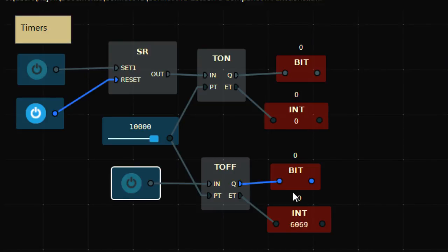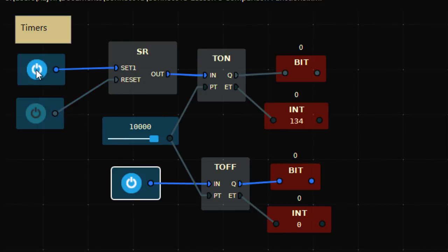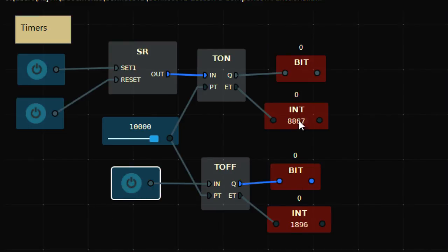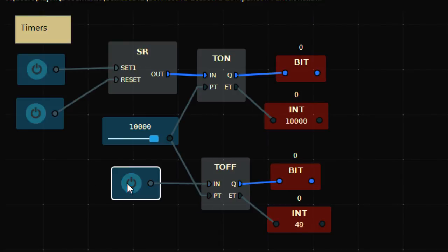So to summarize: T-ON is the On Delay timer — the output turns ON after 10 seconds. T-OFF is the Off Delay timer — the output turns OFF after 10 seconds. That's the only difference. These are the two timers, T-ON and T-OFF, which can be used to add delays in your process logic.